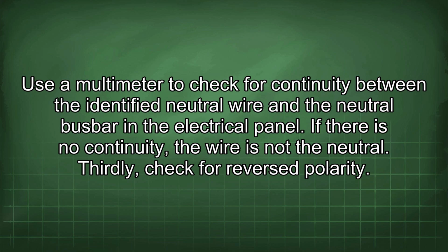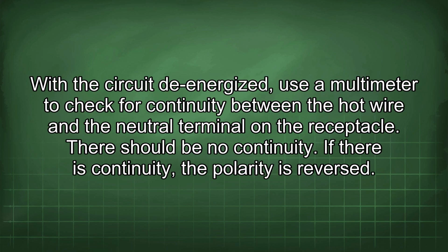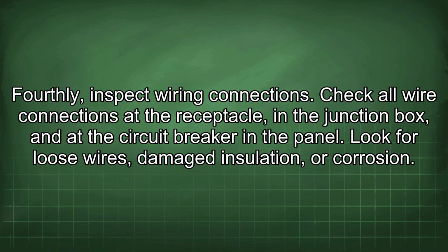Thirdly, check for reverse polarity. With the circuit de-energized, use a multimeter to check for continuity between the hot wire and the neutral terminal on the receptacle. There should be no continuity. If there is continuity, the polarity is reversed. Fourthly, inspect wiring connections. Check all wire connections at the receptacle, in the junction box, and at the circuit breaker in the panel. Look for loose wires, damaged insulation, or corrosion.